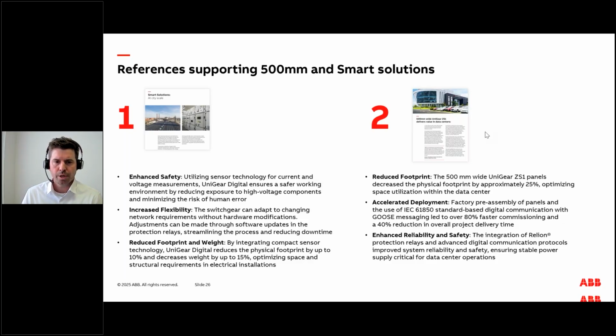In case of the narrower width, in this particular project for a data center customer, you might be able to find the reference either after the webinar communication or available online, where the customer chose to go with 500mm panels for ratings up to 12 kilovolts. It helped them save space and have more space available for IT equipment, which is critical in a data center.